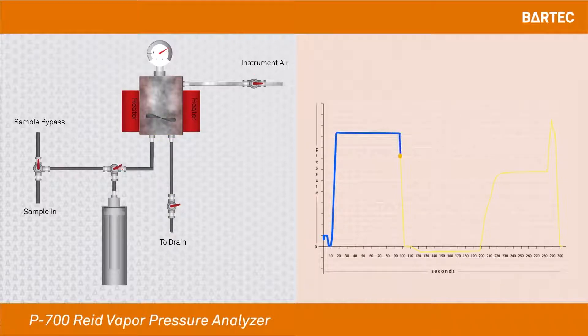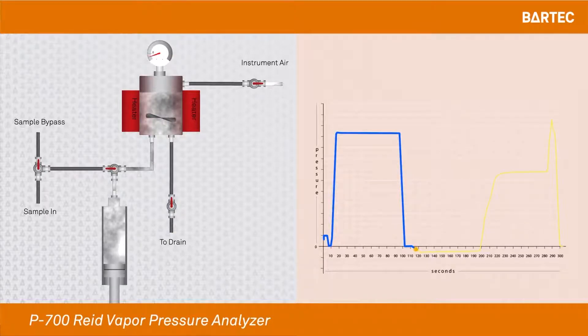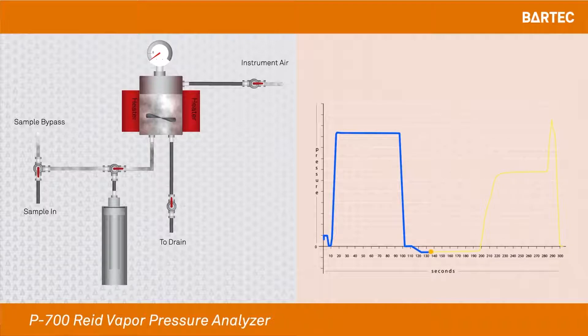We will then open the instrument air to purge any remaining liquid that might be left in the cell. Once the cell is purged, we will then remove one-fifth or one part of the volumes in order to prepare the cell for the 4 to 1 ratio needed to do the RVP measurement.